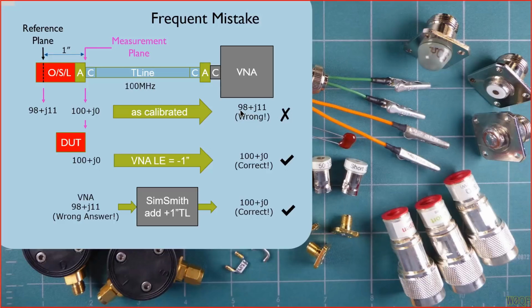However, VNA manufacturers have realized that people don't always make measurements at the reference plane. The reference plane is the most accurate place to make the measurement. Any place else will have small errors that will creep in, but you can't always make it there. Here's an example where I can't make the measurement where I want to make it. So what am I supposed to do? If your VNA software is able to do something called line extension, what you do is you set the VNA up to do line extension. In this case, this VNA would be set up to do 1 inch minus 1 inch of line extension. So instead of extending the reference plane out this way, we're going to bring it back 1 inch.